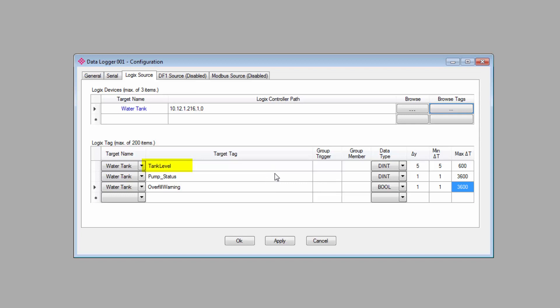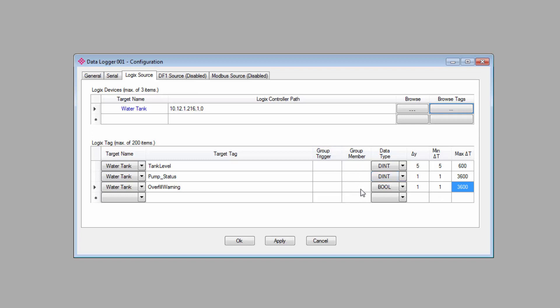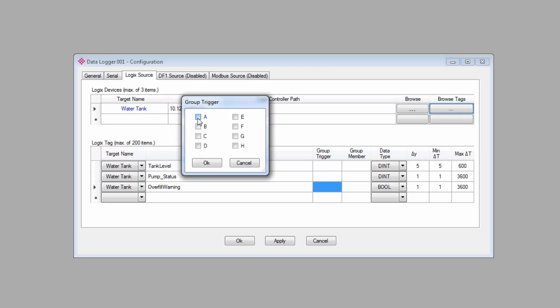So, in my example, I have a tank level reading, I have an overfill warning that will flip on when the tank is nearing full capacity, and I also have a pump status tag that lets me know when the pump that fills the tank turns on or off. I can use the frequency and timing features to set up when to log data for each of these tags independently, but I can also use the group features to ensure all the data that I might need gets logged at the right time. I'd like to ensure that I always have a reading of the tank level anytime the overfill warning turns on or when the pump turns on or off.